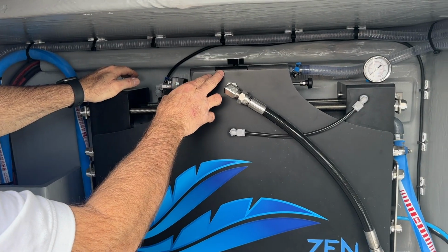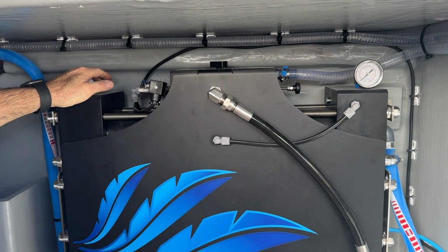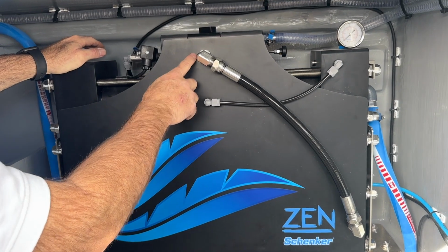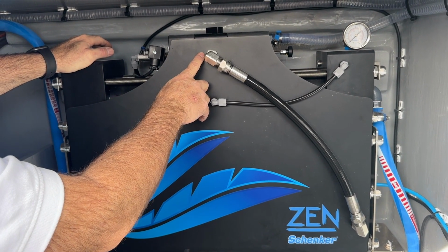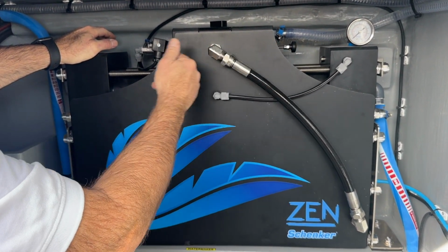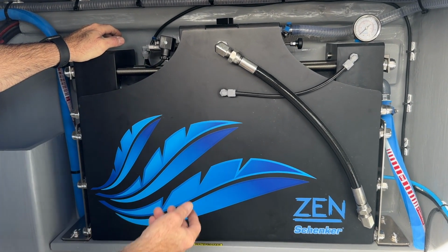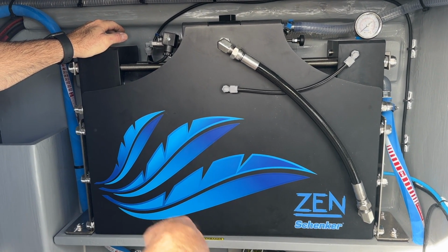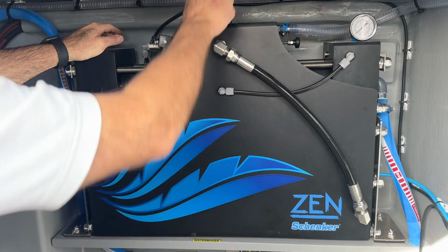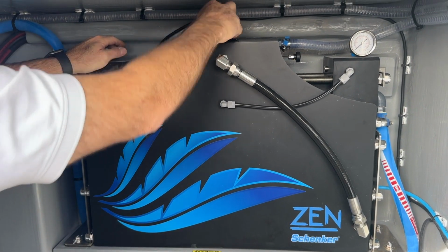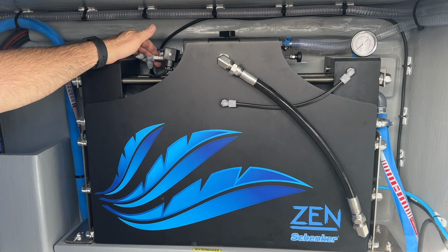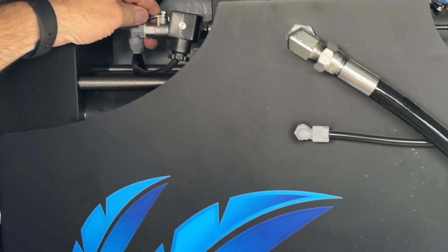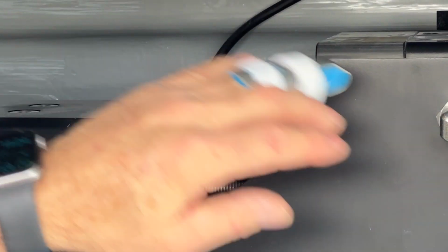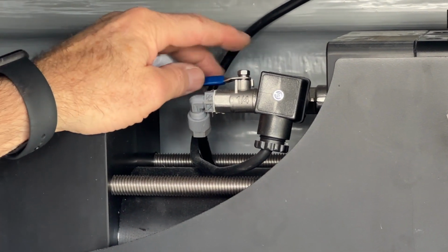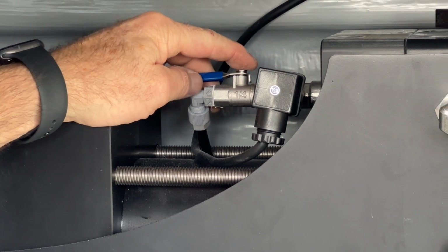In the unlikely event that the spool ends in the center position, the water coming from the pump physically can't go past this point. So we then need to mechanically move the spool over the center position. This will only occur if the unit is shut down outside of its normal operation. In order to do this, we need to open up the thumb screw by a full turn. We need to open up what we call the reset valve. This allows any water trapped in front of the spool when we push it across to expel itself. At most you're going to get a teaspoon of water out here.